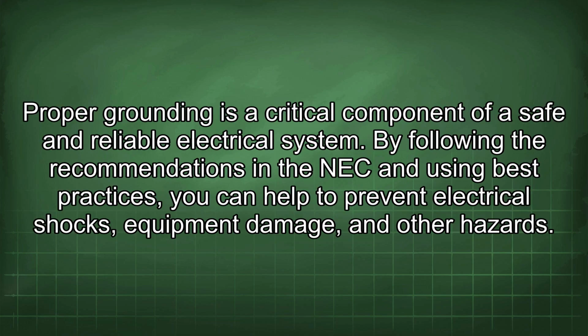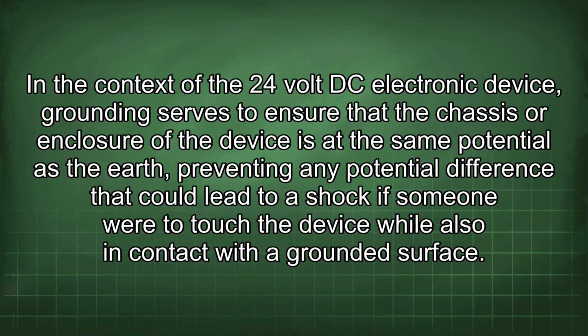Proper grounding is a critical component of a safe and reliable electrical system. By following the recommendations in the NEC and using best practices, you can help to prevent electrical shocks, equipment damage, and other hazards. In the context of the 24-volt DC electronic device, grounding serves to ensure that the chassis or enclosure of the device is at the same potential as the earth, preventing any potential difference that could lead to a shock if someone were to touch the device while also in contact with a grounded surface.